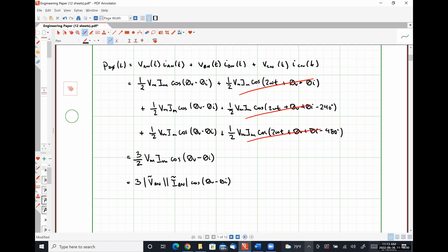This is one of the biggest reasons why three-phase loads are used in industrial settings. If the power delivered by a three-phase load is constant and we're hooking it up to something like an induction motor, then the torque that the motor experiences is constant, which means it operates at a minimum possible level of vibrations, giving us the least amount of potential opportunities for mechanical deformation. There is a very specific reason why the three-phase electric machines in our power labs — some of which predate World War II — are still in operation. They experience very little opportunity to be damaged when connected to a three-phase system.